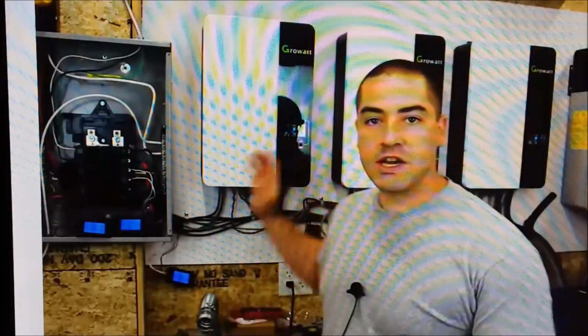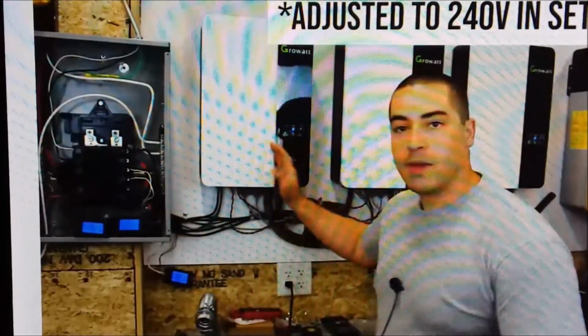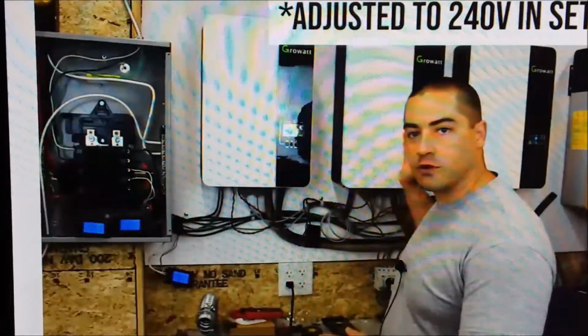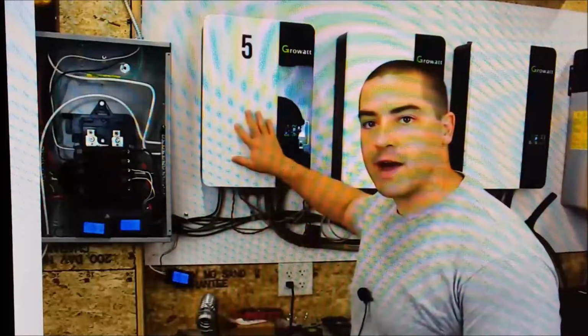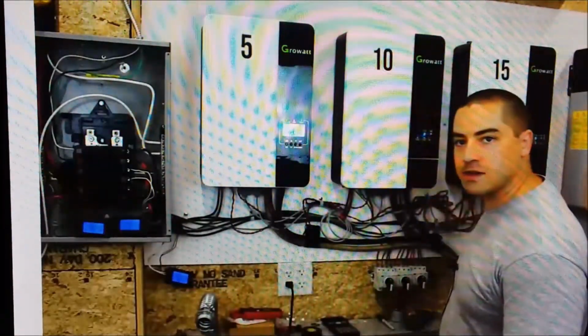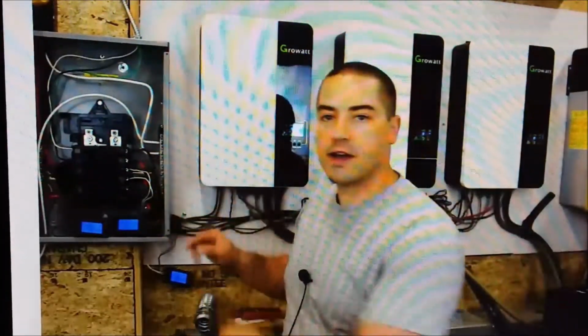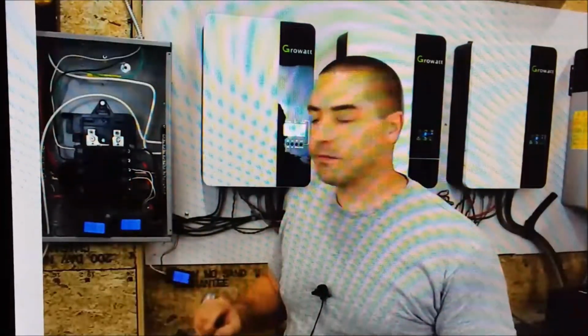Now these inverters each output 230 volts, and then we paralleled them, so we're still at 230 volts, but we're just increasing our total capacity. So 5 kilowatts, 10 kilowatts, and 15 kilowatts, all feeding together into this one load center.